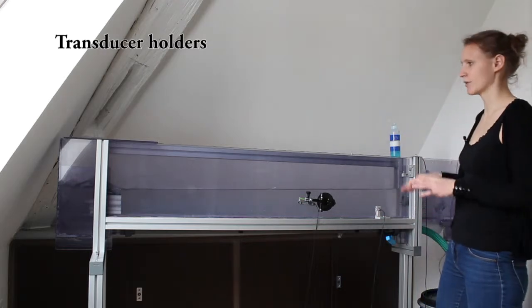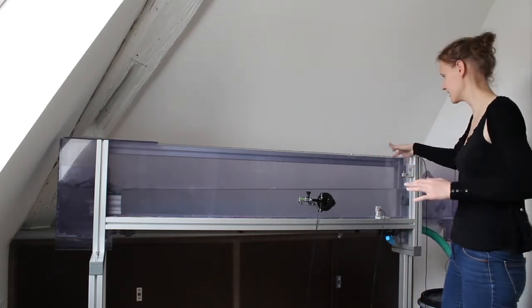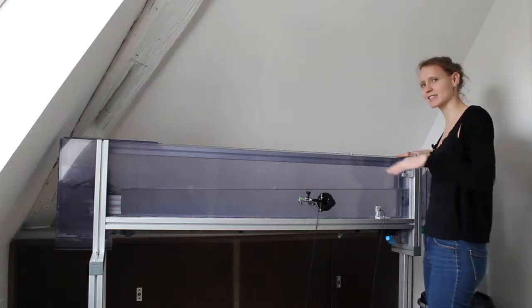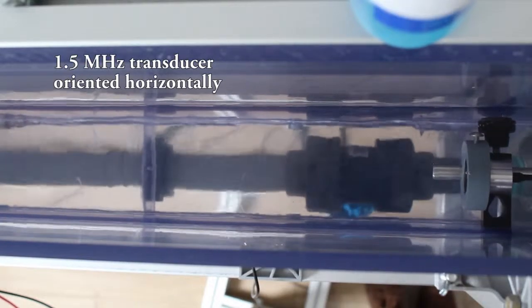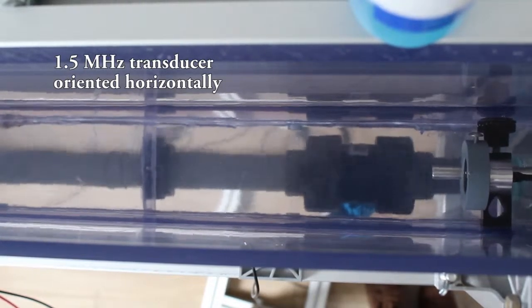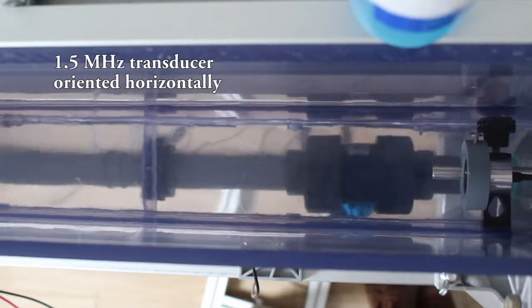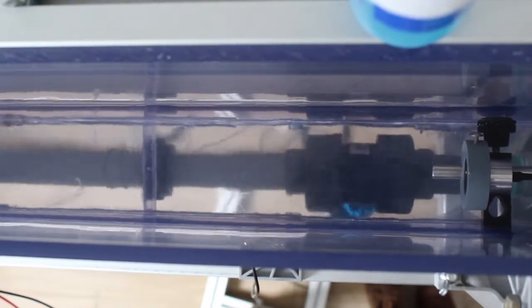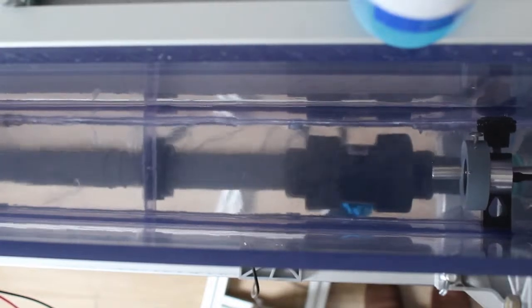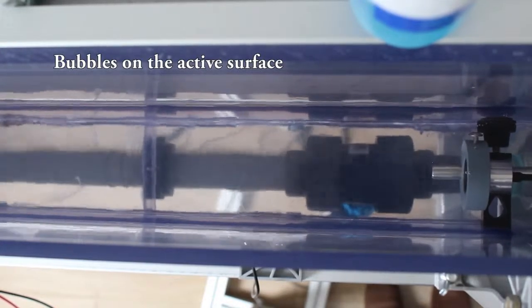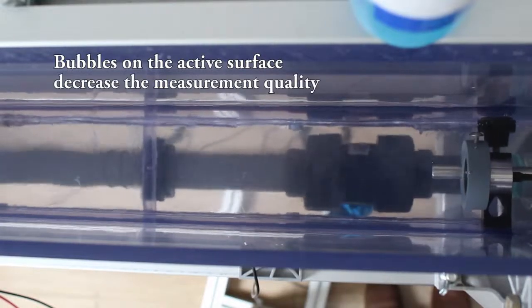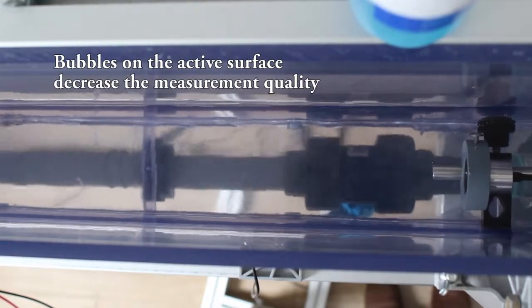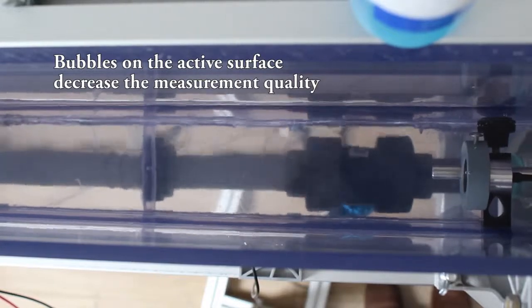You can put a holder directly in the liquid. The first idea is this one. Let's look at it closer. Here you have a quite simple holder. The 1.5 MHz transducer is oriented horizontally towards upstream. The UB Lab measures a velocity profile along this axis, which looks like this. You will have to pay attention that there are not too many bubbles attaching to the active surface. Bubble formation will decrease the quality of the signal, air having a low acoustic impedance.